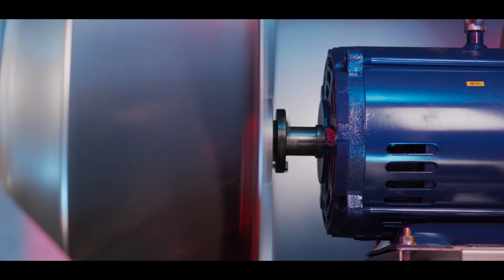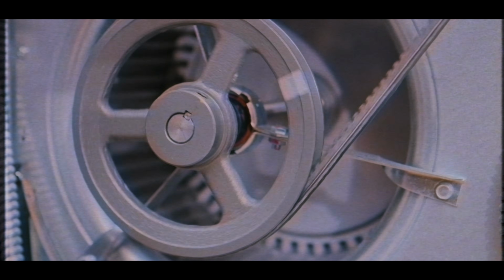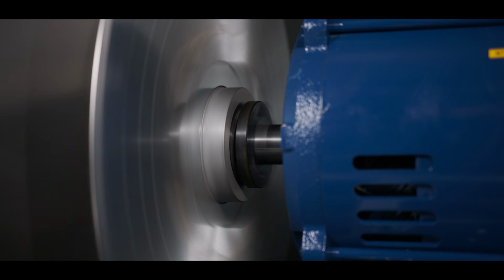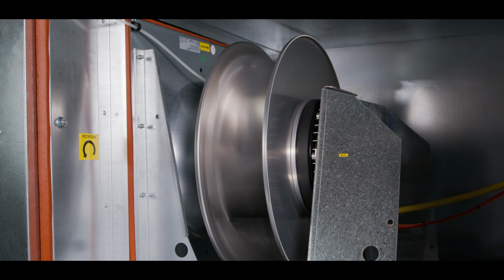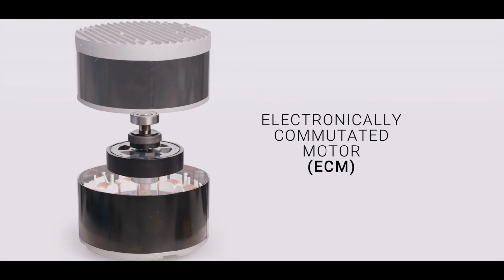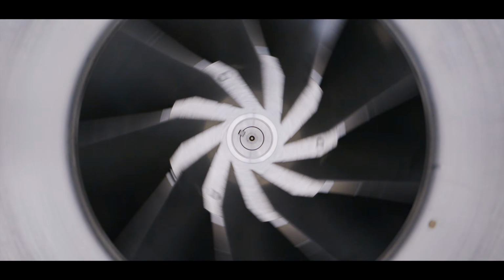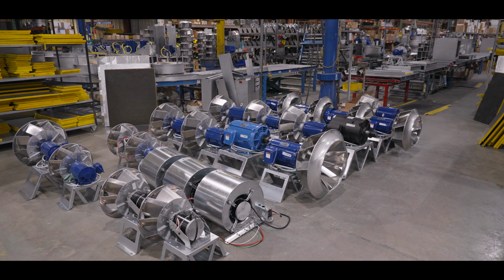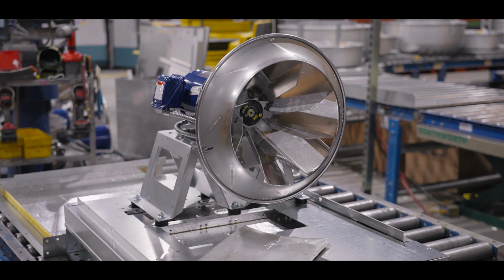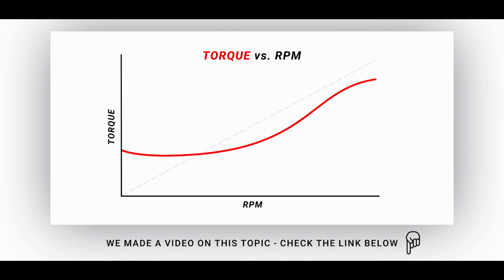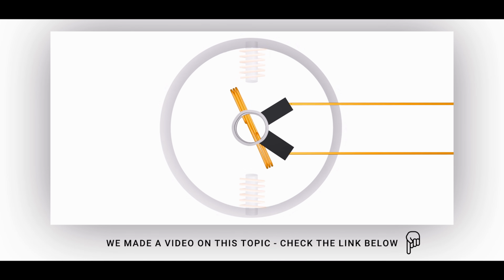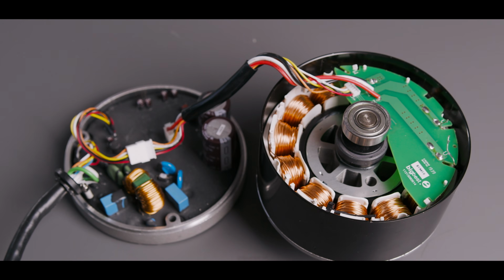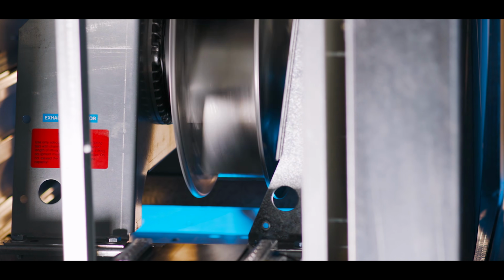At this point in my career, I've realized that belts are designed to fail. So if you have a belt-driven HVAC unit, you are actually designing failure into the unit. With direct drive blowers, there's no belt present, so you've eliminated that failure mode. We use a mixture of electronically commutated motors and high-efficiency AC motors to create the best possible energy and longevity solutions for the equipment. Not every 10 horsepower motor is created equally. There's different torque curves and different electrical characteristics, so we have to know that data, and we have to make good engineering judgment on which motor is going to perform best in this equipment.